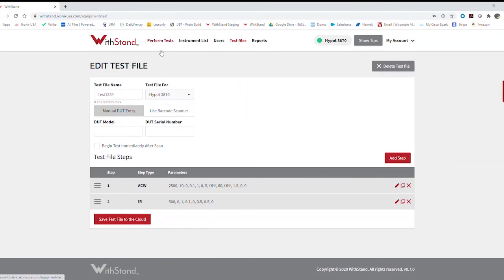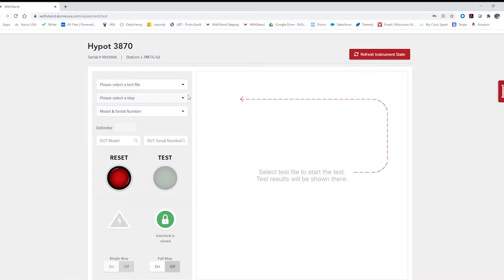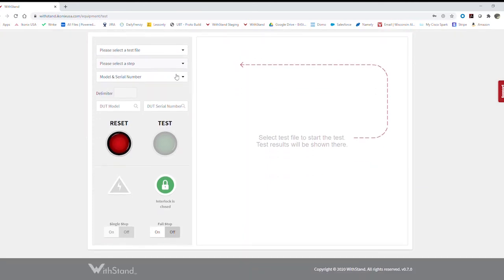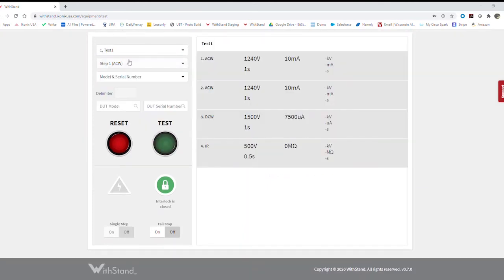Next, I would just go ahead and run the test. Now from here, I can see that I can select any test file that I've created. So I'll just go ahead and select this one. And I can also see that I have my interlock status showing me that my interlock is in fact closed and the instrument is safe to use.